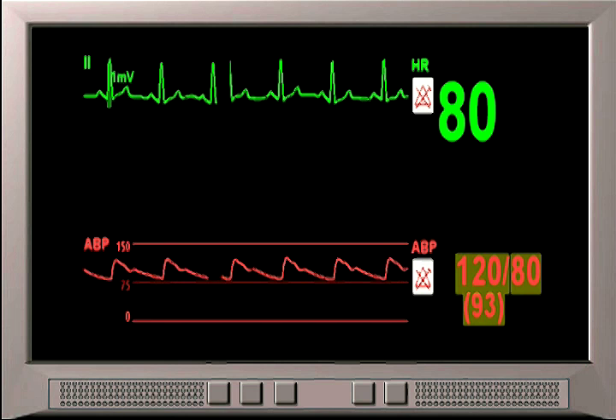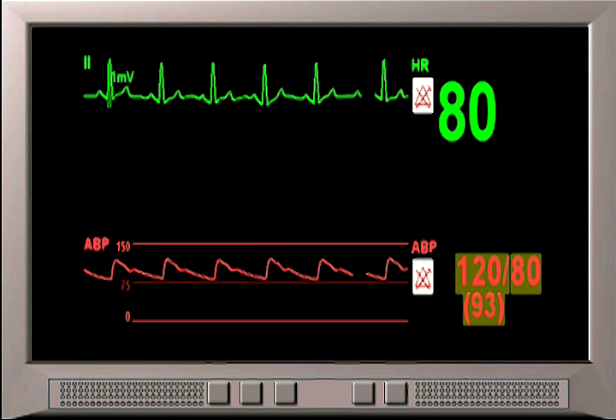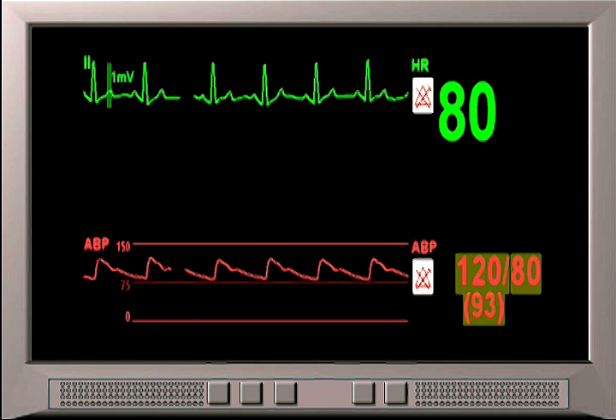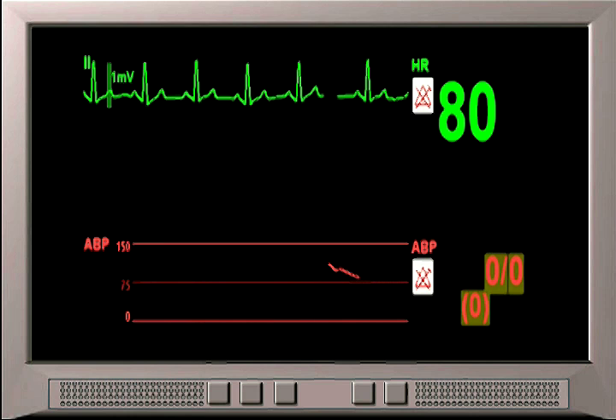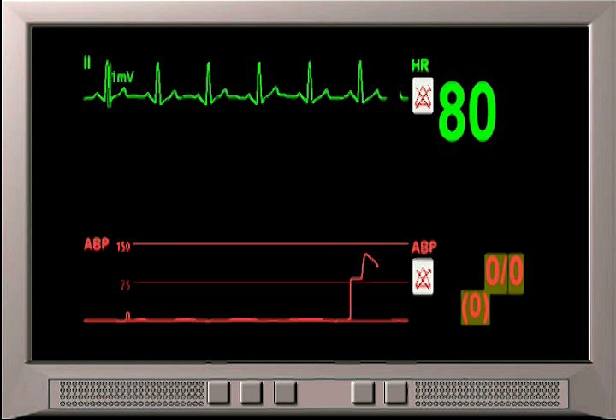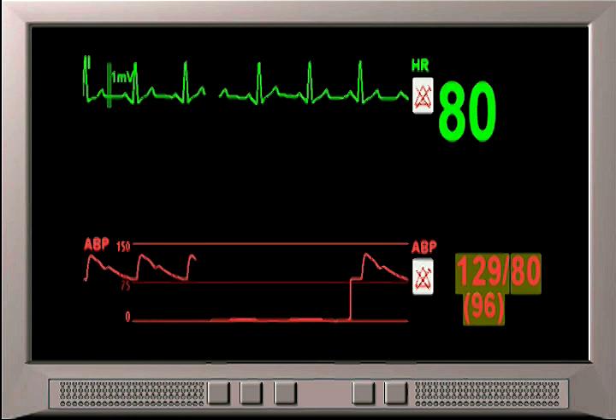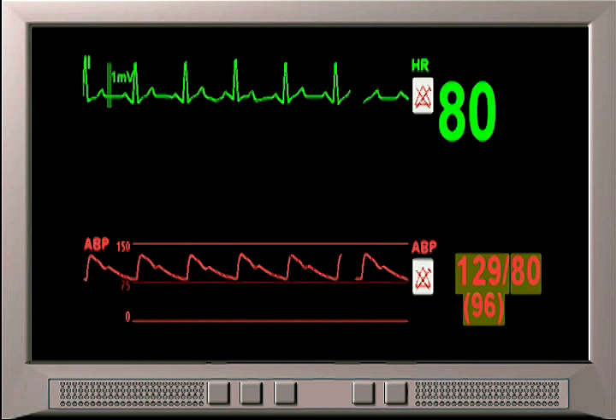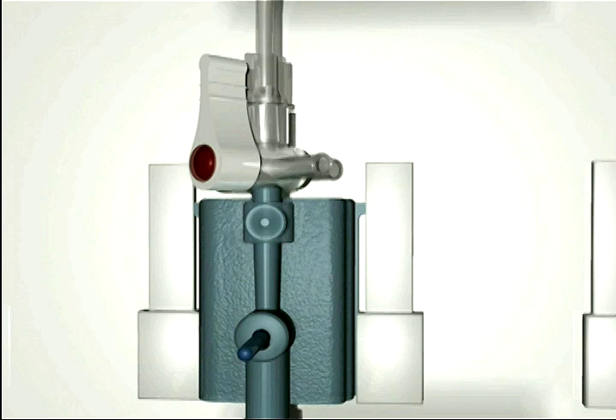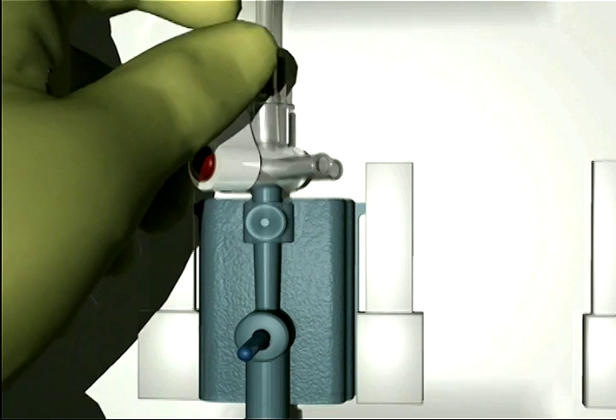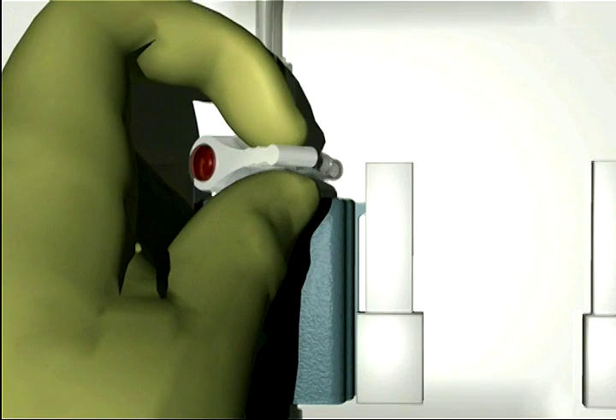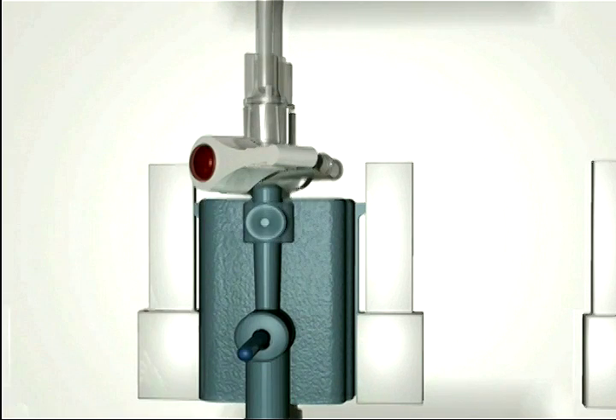Step 4. Select the zero function on the bedside monitor and confirm that the bedside monitor's pressure channel waveform and numeric value display 0. Step 5. Close the stopcock on the TruWave transducer toward the vent port and then return the non-vented cap.